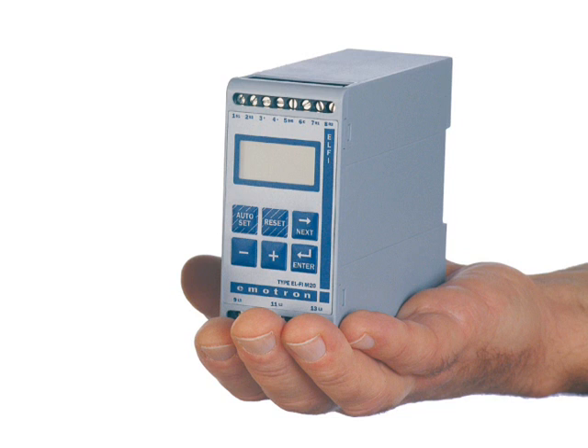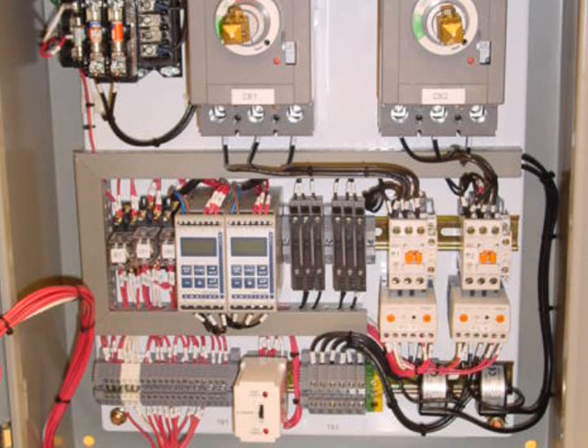The Emotron M20 uses the motor as a sensor and a unique algorithm to calculate the output shaft power. This patented feature of the M20 makes it the most advanced motor load monitor available, and allows us to reliably protect the driven equipment against abnormal overload or under load conditions. More than 500,000 Emotron load monitors are being used throughout the world to protect motor driven equipment and to help maintain production uptime.